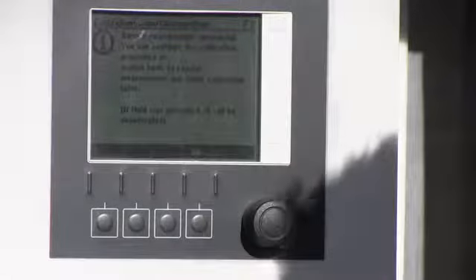We hit OK. The transmitter will prompt us. It says, please clean the sensor before beginning the process. You can ignore this step. There's no need to clean the sensor. It's in the flow block. Hit OK. It gives you the raw measured value coming off the sensor. It says waiting for stabilized measured value. The transmitter wants to make sure that the output from the chlorine sensor is stable before we attempt to do a new calibration. After it does that, it says sample measurement successful. You can continue the calibration.